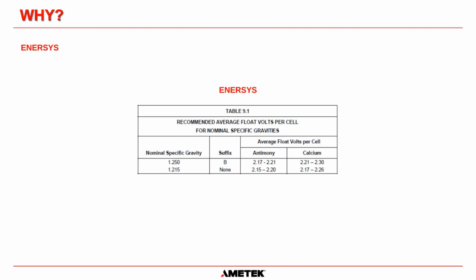So I mentioned that it's manufacturer specific. For EnerSys, I just picked out, I can't remember which cell this was, but this was a specific type of EnerSys cell. They give two versions of this monoblock here, depending on whether the specific gravity of the cell is 1.25. It also matters if it's an antimony cell, and I'm not going to go into the difference, but basically it's the difference of the plate grid. The majority of plate grids, which is how the lead is pasted into the battery, are calcium, but there are some out there that are antimony or low antimony.